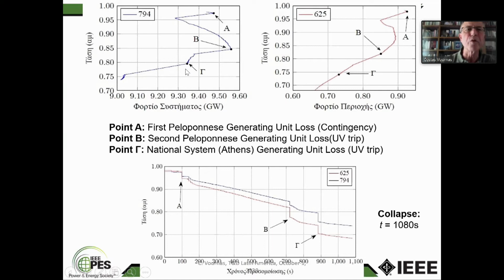And at point gamma, you have the loss of one generating unit in the Athens area, and then the system collapses. Now, this is the national curve. This here is the PV curve of Peloponnese. You see it's above 0.9, 900 something, 925 megawatts.